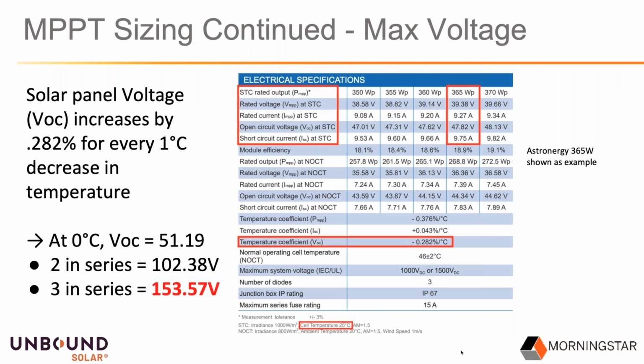Let's go over a quick string sizing example. And this will show you how you can calculate max voltage from a solar panel. I have a solar panel spec sheet here. This is probably a lot of information, so I tried to highlight a couple of things in red rectangles. We have the solar panel power specs, the watts, volts, amps, and then we have a temperature coefficient highlighted towards the middle. And then towards the bottom, I circled the cell temperature of 25 degrees C, which is what all this is based off of. So what does all that mean? This solar panel, it's a 365 watt Astronergy panel in this case. It's going to produce 39.38 volts max power, 47.82 volts open circuit, and then just under 10 amps, depending on the current rating we're looking at.